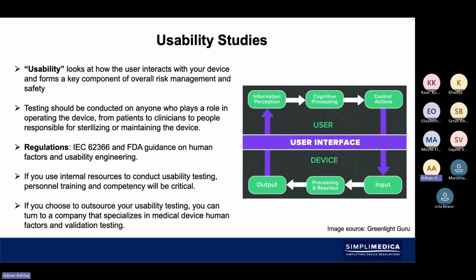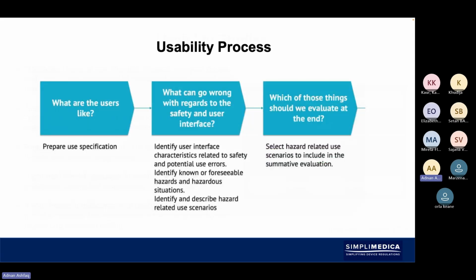Then we look at usability, which is also very, very important. So the usability of the device, we need to also then conform to IEC 62366, and then also FDA guidance for human factors. You might need to perform formative evaluation or summative evaluation or both, and that's to attain feedback. What are the users like? You need to prepare a use specification. What can go wrong with regards to the safety and the user interface?